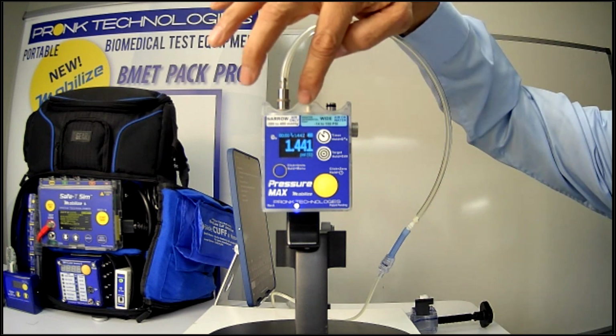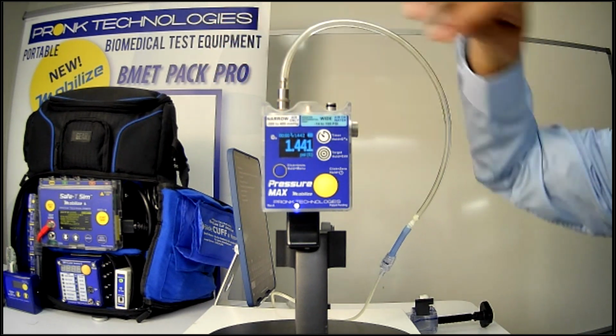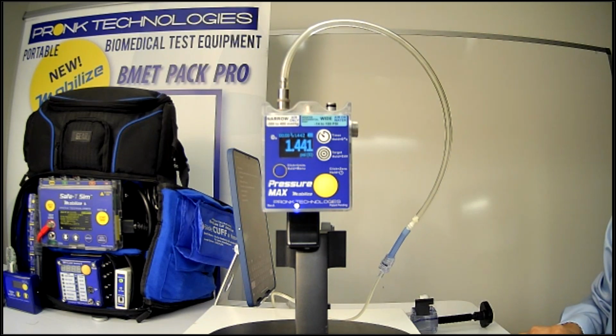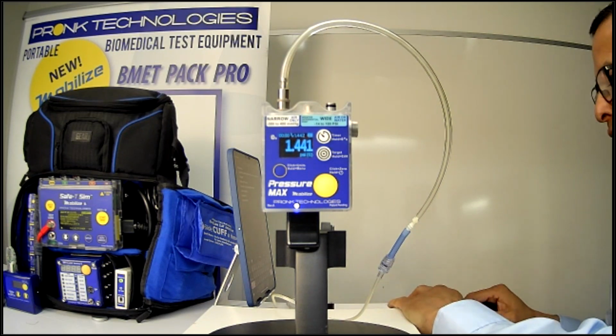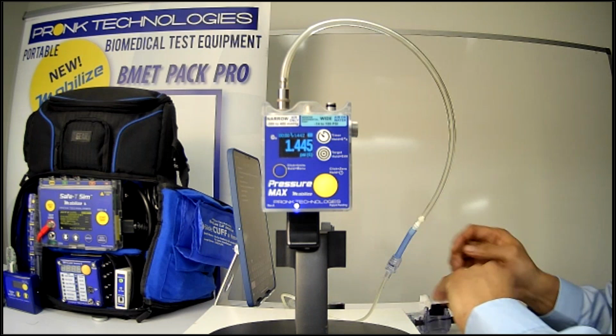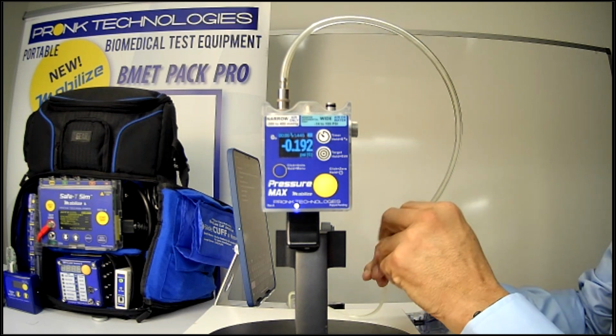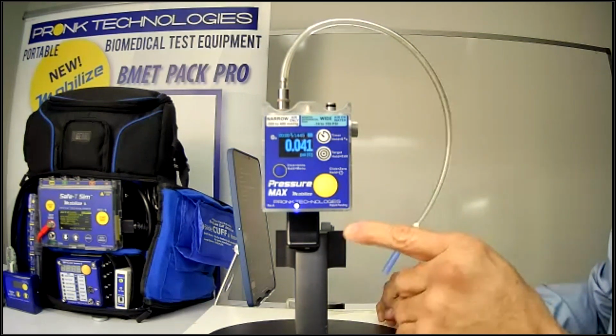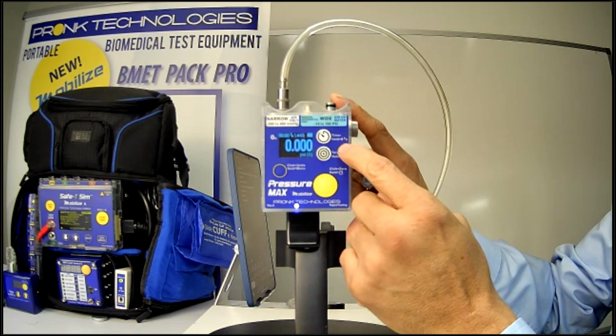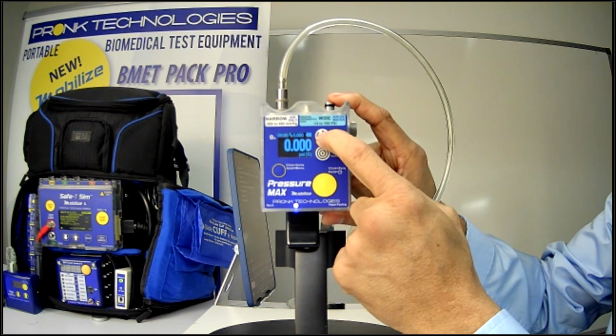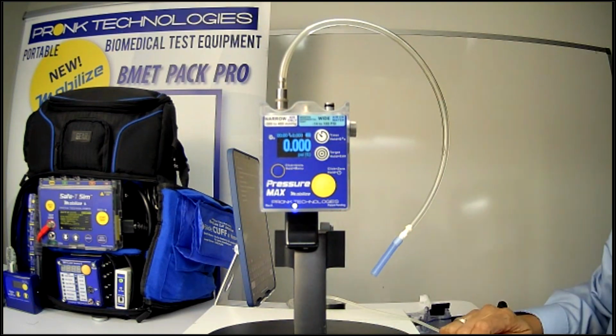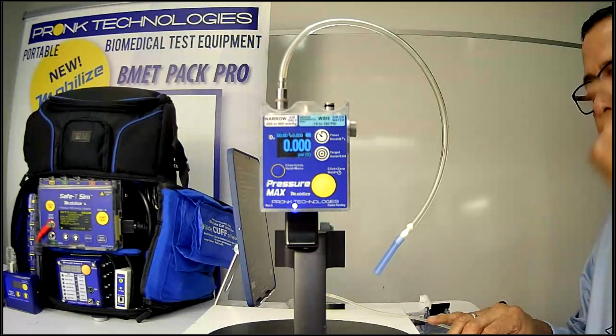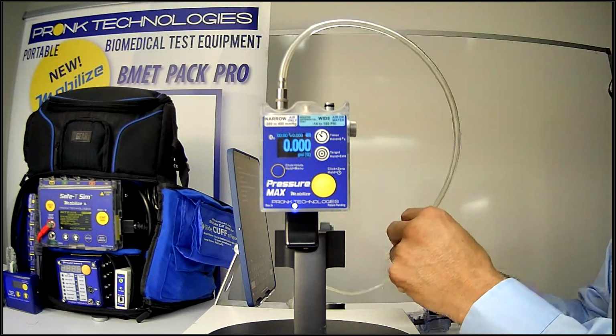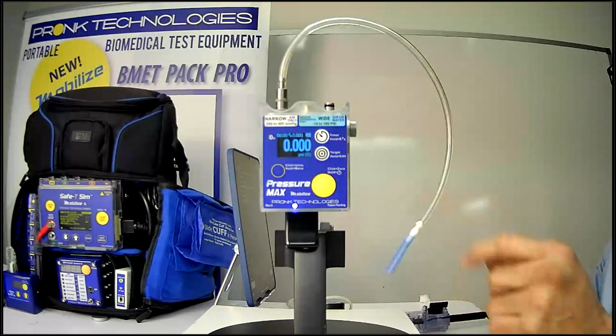You can see here at the top, I captured a peak pressure that's being illuminated at the top, so that stays and locks in there. I could choose to zero that pressure if I want to. I'll open up to atmospheric pressure, and I could press and hold the timer button and zero out that peak pressure. So it's really easy to use that narrow port for measuring pressure.